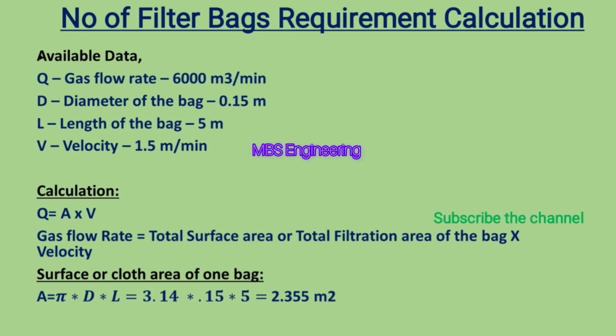Next, we are going to understand how to calculate the number of filter bags required in the bag filter system. Available data: Q, gas flow rate 6000 m3 per minute; D, diameter of the bag 0.15 meters; L, length of the bag 5 meters; V, velocity 1.5 meters per minute.